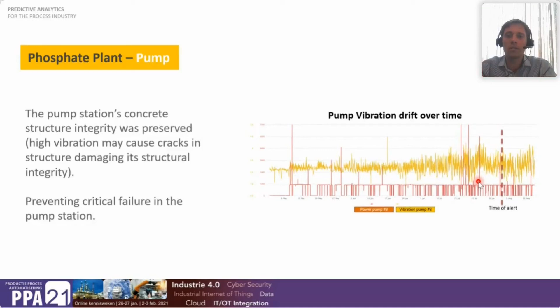No more issues. But if we were not there, the cracks would become bigger and bigger, this specific pump would probably fail, and then maybe the other 4 pumps over there would also get damaged. So again, the cost here was $1,000 or $2,000 for them to fix the issue, but the potential loss of what could have happened if this pump, or the whole pump station, was completely destroyed - that's within the millions.